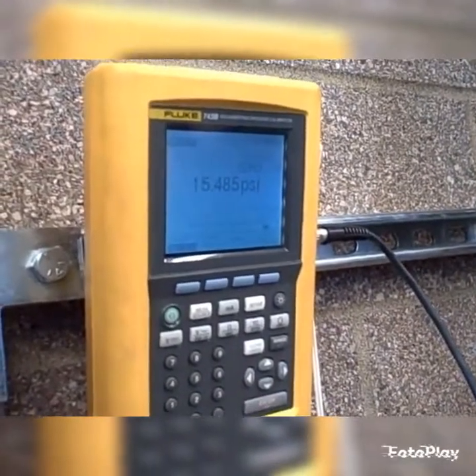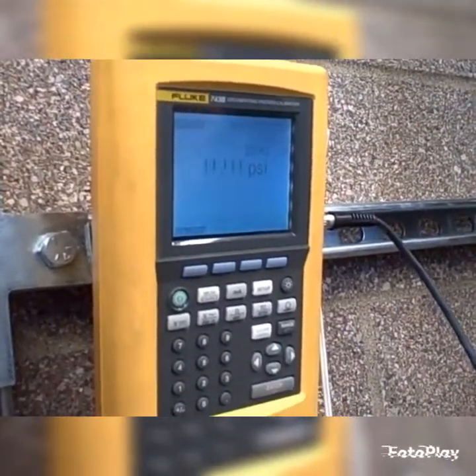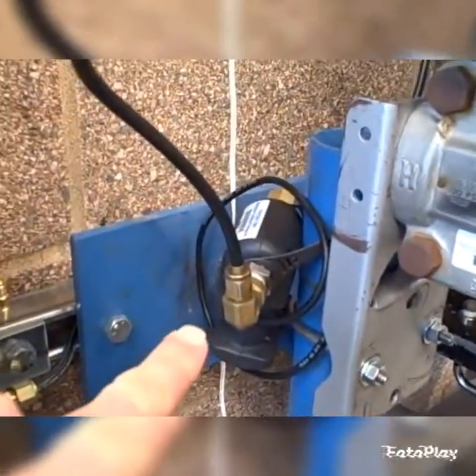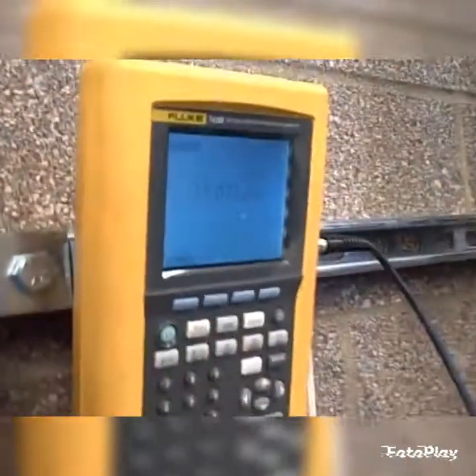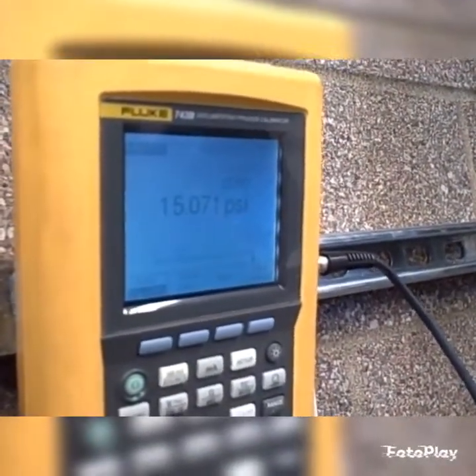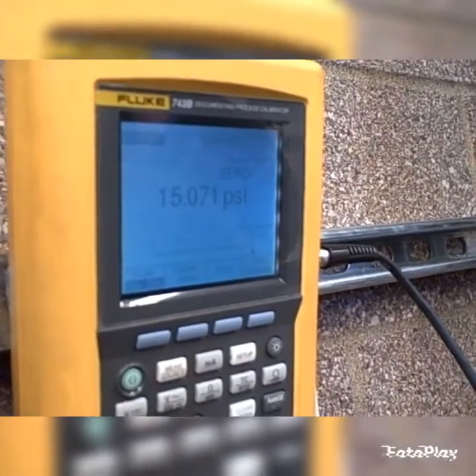We're using a pressure module here, the Fluke 743, that has an upper range limit of 15 psi. As a consequence, every time the output pressure of this DP cell goes significantly above 15, this shows exclamation marks — it goes over range — like it's about to do right now as Shane puts his wrench on it.